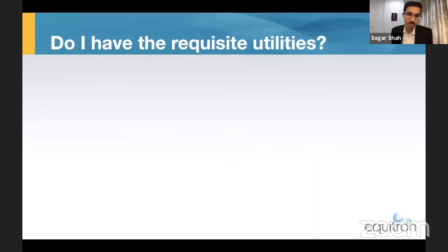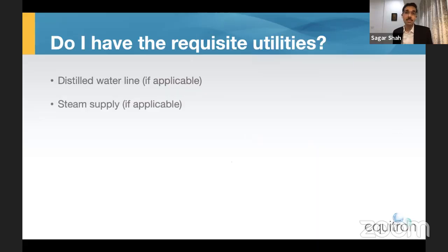Now, have you properly checked the utilities that the autoclave requires? And have you checked the specification or the parameters of those utilities? If you're opting for an autoclave with automatic water filling facility, it would need a distilled water line as well. And that distilled water line should be capable of providing dynamic pressure as per the manufacturer's requirements. If you have your own site steam supply, you may also want to check with the manufacturer whether the selected autoclave can be connected to your steam supply.